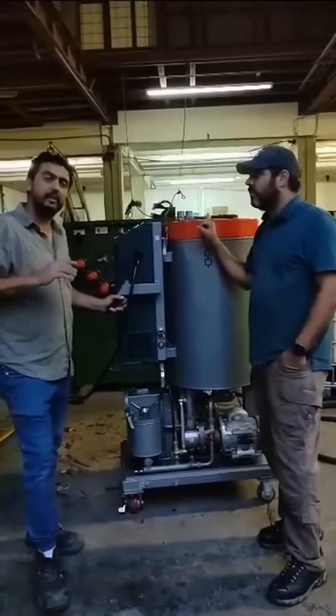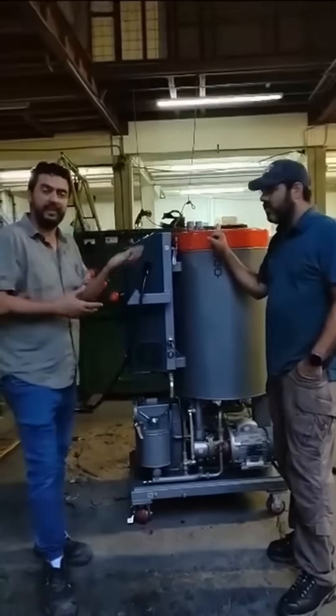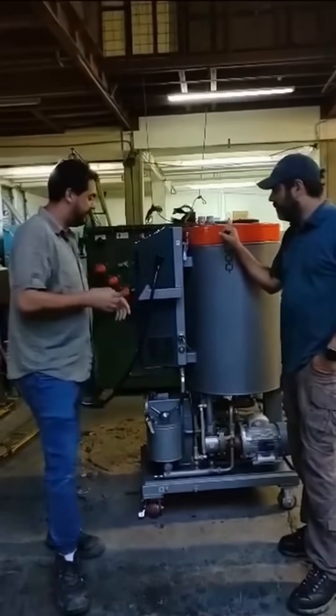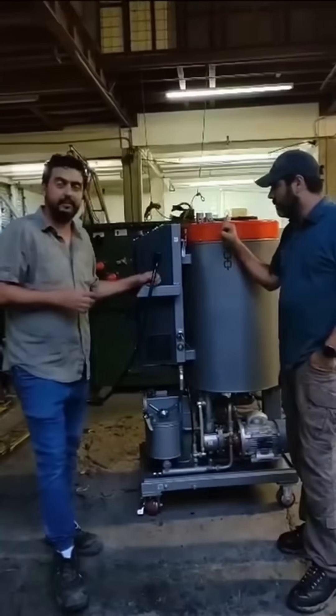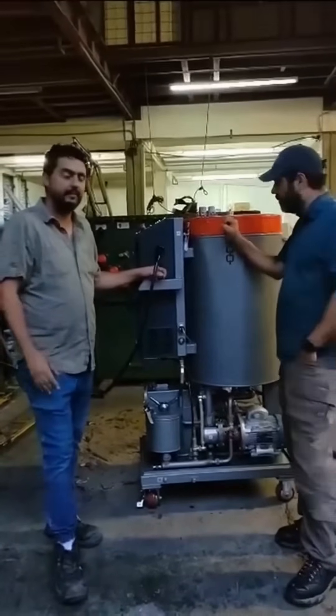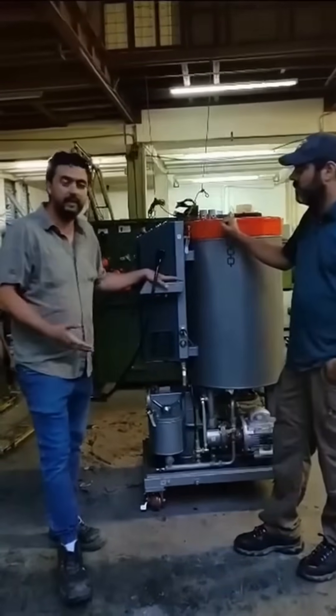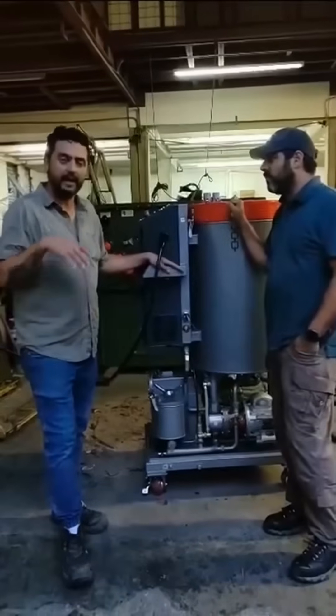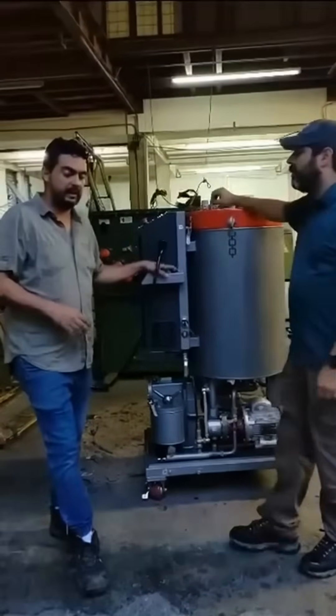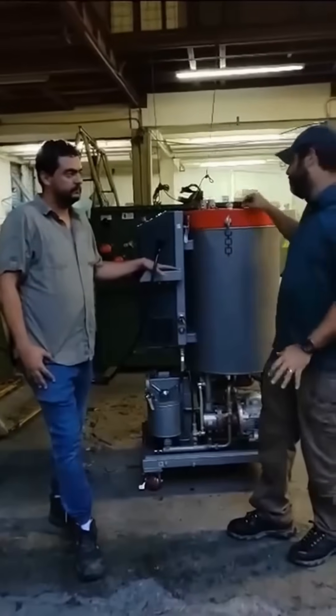After making 2,000 passes, we are currently working on a 1,000 kVA transformer, 34,500 volts to 480 volts. It is a transformer that was changed to biodegradable oil and we are also working to additionally increase the dielectric rigidity of the transformer itself. KVP is dedicated to maintaining and extending the lifespan of transformers, as well as repairing them.